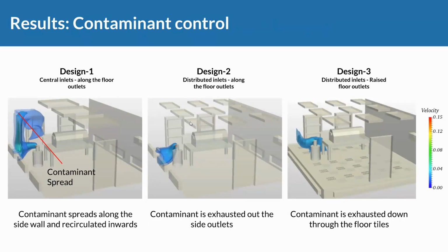And that's now visualized here. That's a contour plot or isosurface plot of different levels of contaminant concentration. Wherever you see a blue surface, contaminant has spread there. Let's assume again that's some dangerous species flowing around here. In the left scenario, as we suspected, the species enters the recirculation area at the top and can spread around. In the other two scenarios, we can see that the contaminant is much more effectively removed, right?